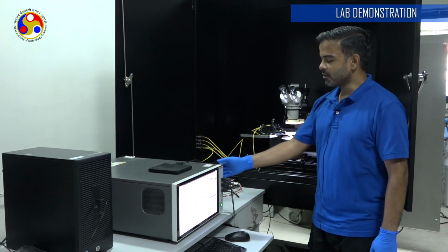SMU 1 and 2 are capable of measuring low currents up to the femtoampere range. SMU 3 and 4 are capable of conducting high voltage measurements. Apart from IV, it can measure capacitance voltage as well as pulse measurements.